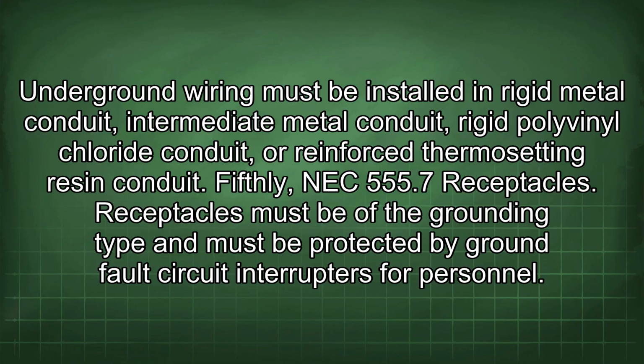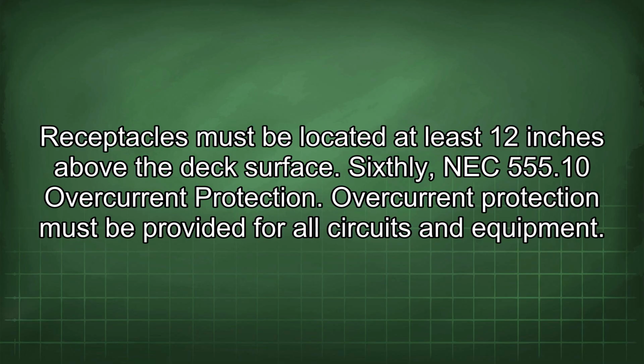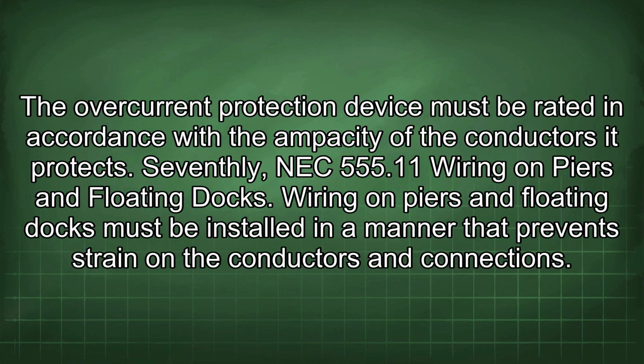Fifthly, NEC 555.7 Receptacles. Receptacles must be of the grounding type and must be protected by ground fault circuit interrupters for personnel. Receptacles must be located at least 12 inches above the deck surface. Sixthly, NEC 555.10 Overcurrent Protection. Overcurrent protection must be provided for all circuits and equipment. The overcurrent protection device must be rated in accordance with the ampacity of the conductors it protects.